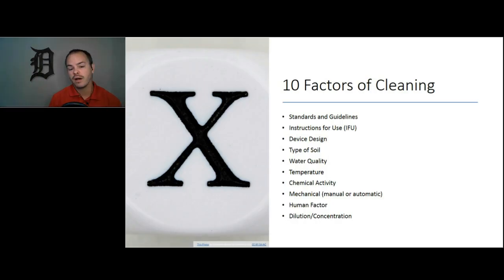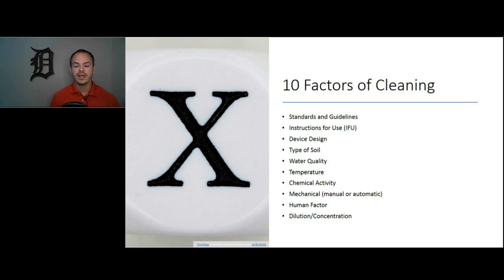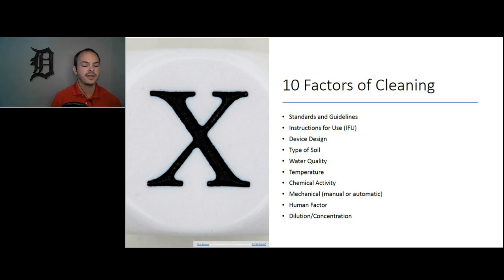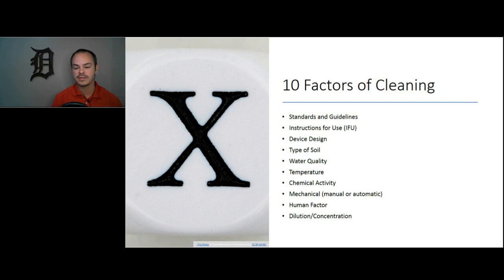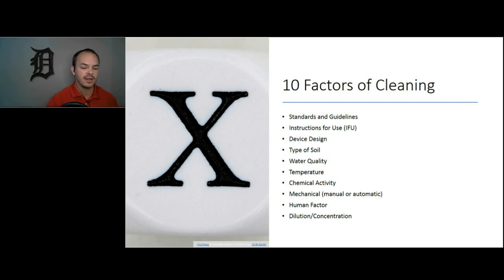Manual and automated cleaning processes are great when they work, but both machines and people are subject to failing. There are ten factors that can cause the cleaning process to fail: standards and guidelines not built into your process, instructions for use not available or outdated, the type of soil such as blood or synovial fluid, temperature, chemical activity of your detergents, dilution concentration of detergent, human factors, and mechanical factors whether manual or automated. There are a lot of different ways we can go wrong in our cleaning process.